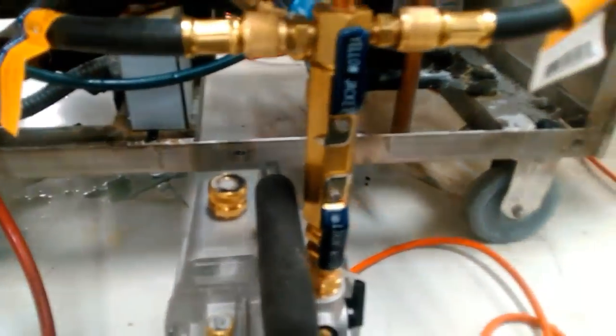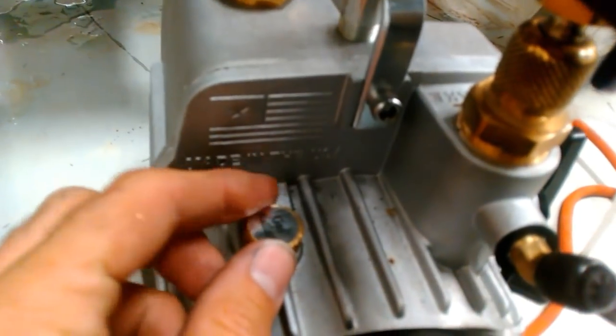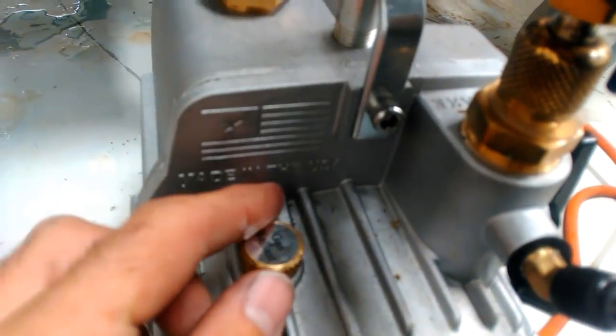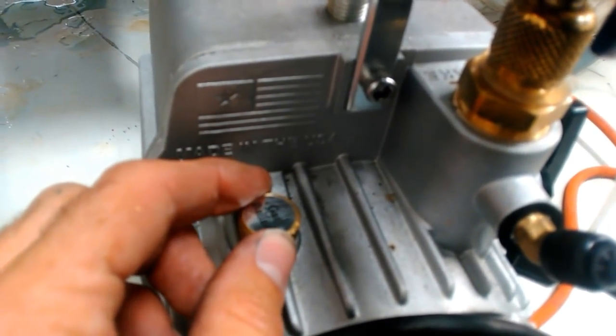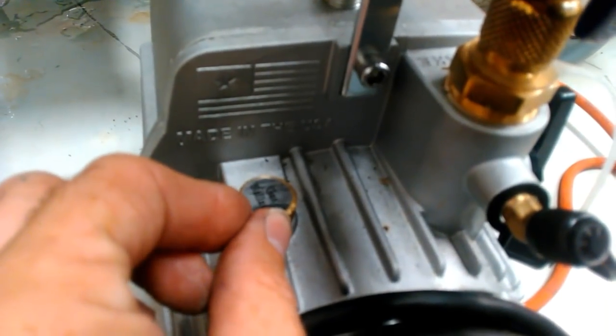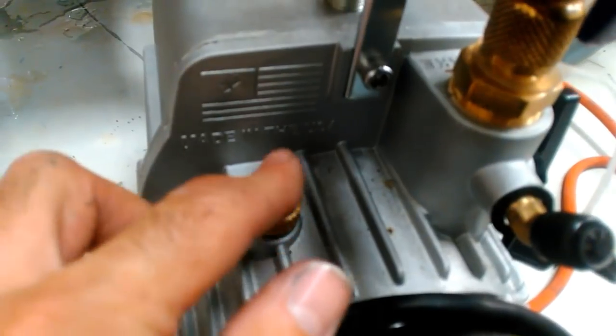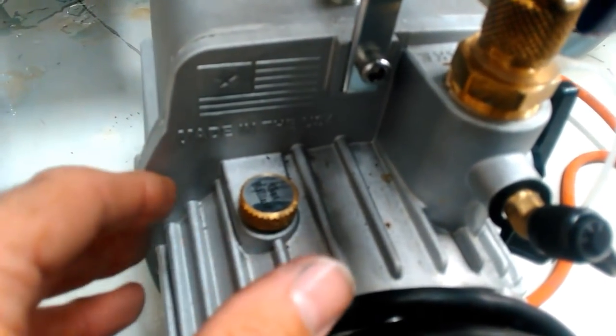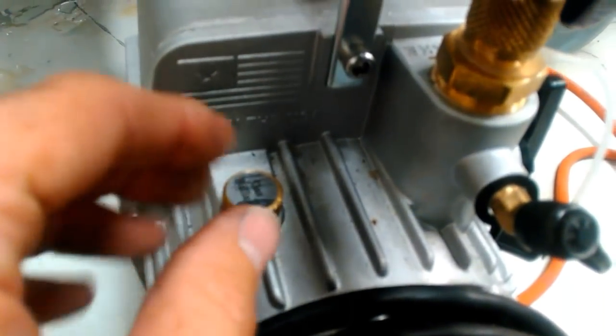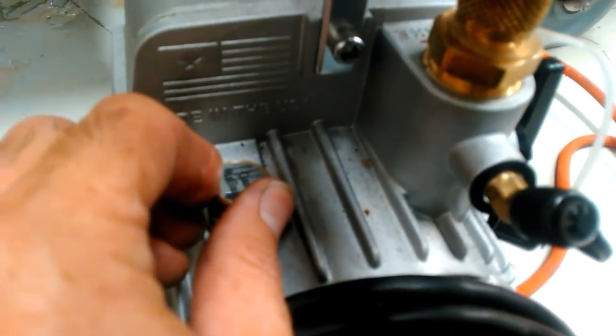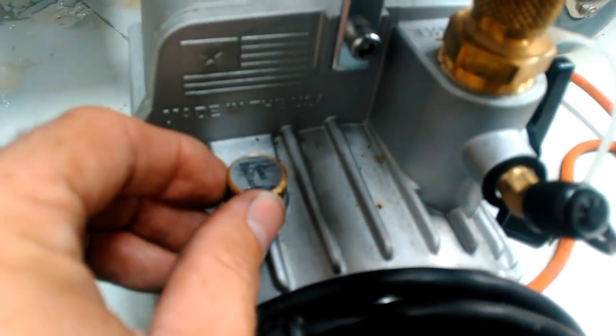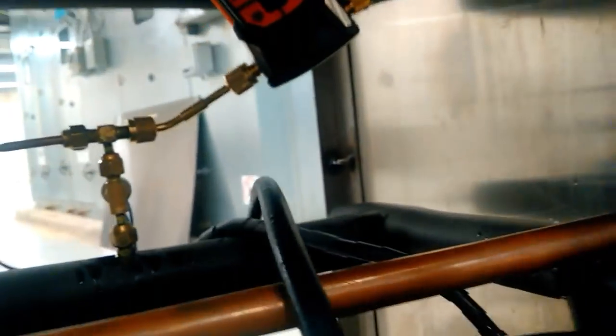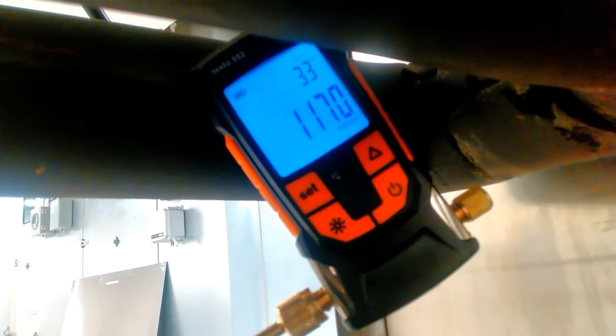When you start your vacuum pump up, you want to crack the gas ballast. The instructions state down to about 2,000 microns, I believe. When you crack this gas ballast, you're basically bypassing the oil. Some of the air is bypassing the oil, and that preserves your oil from getting contaminated. When you hit about 2,000 microns, you close this up. Now you let that oil grab the contaminants, and that will pull your vacuum down much faster. We can check the status of our vacuum right now. We're at 1,100 microns and we're steadily dropping.